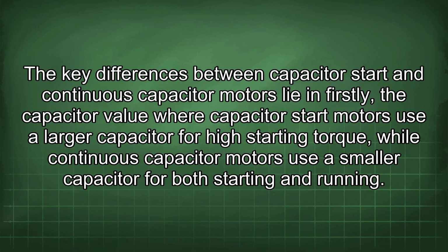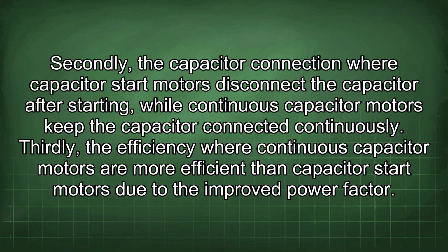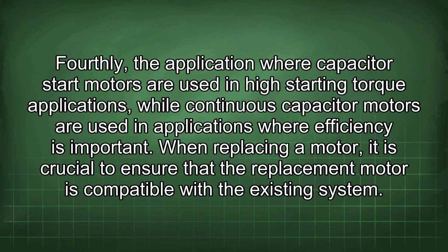The key differences between capacitor start and continuous capacitor motors lie in, firstly, the capacitor value, where capacitor start motors use a larger capacitor for high starting torque, while continuous capacitor motors use a smaller capacitor for both starting and running. Secondly, the capacitor connection, where capacitor start motors disconnect the capacitor after starting, while continuous capacitor motors keep the capacitor connected continuously. Thirdly, the efficiency, where continuous capacitor motors are more efficient than capacitor start motors due to the improved power factor. Fourthly, the application, where capacitor start motors are used in high starting torque applications, while continuous capacitor motors are used in applications where efficiency is important.